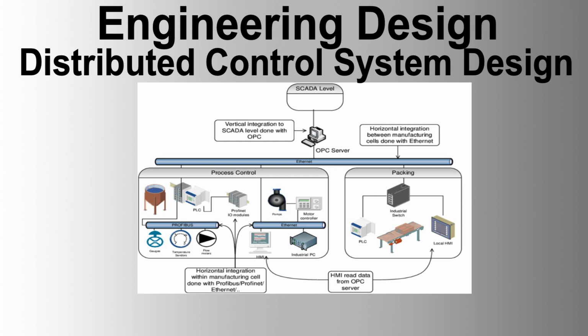Hardware requirement. 1. General. The system must allow card replacement without switching off power or disturbing the process. Short-circuiting of individual inputs and outputs should not affect other inputs and outputs. Theoretical failure rate figures for all boards, power supply units, and other functional subassemblies must be provided. Anti-static precautions, if necessary, should be indicated and grounding wrist straps supplied. The entire system must be RFI immune.